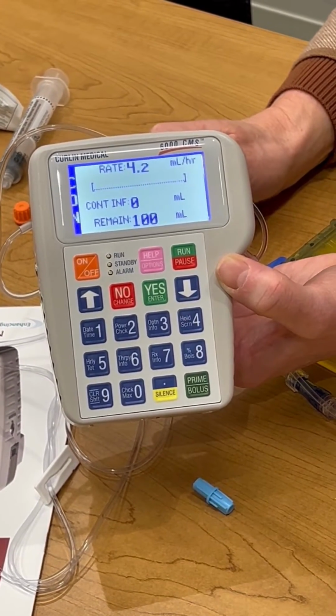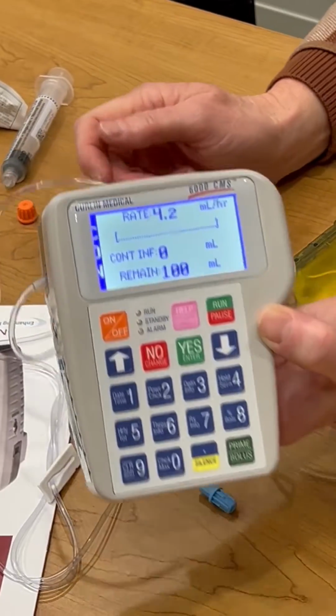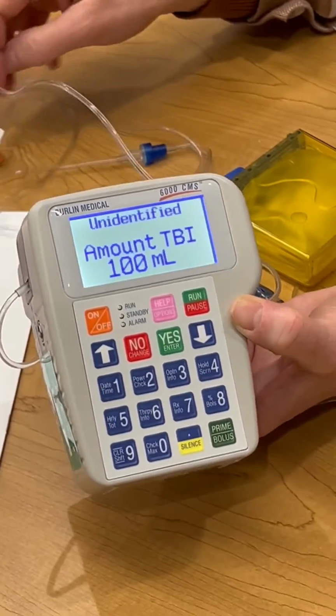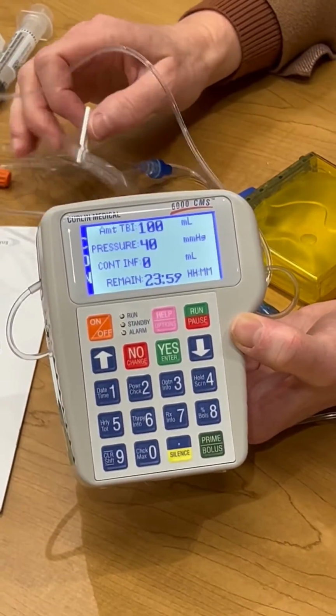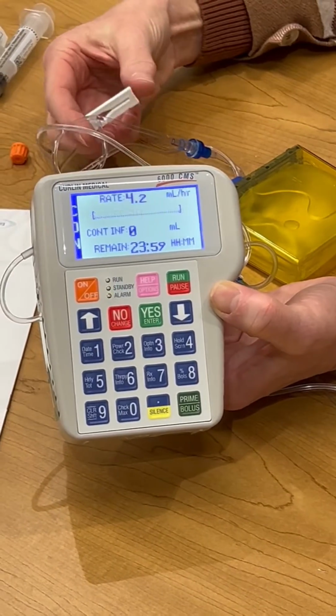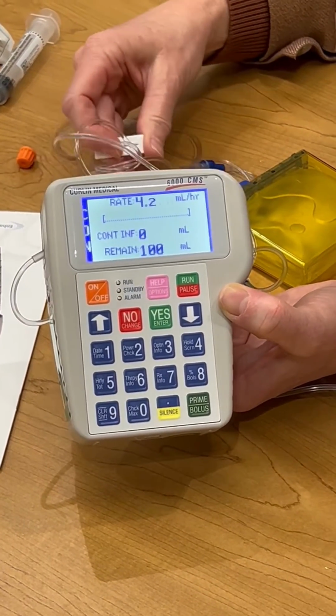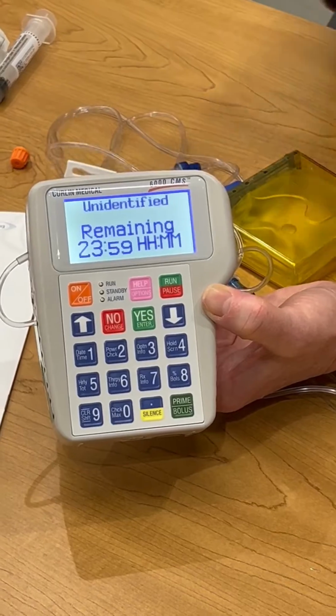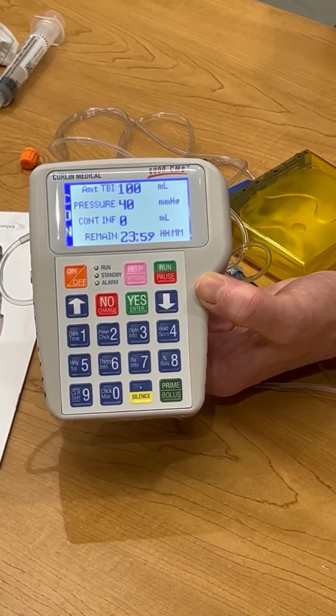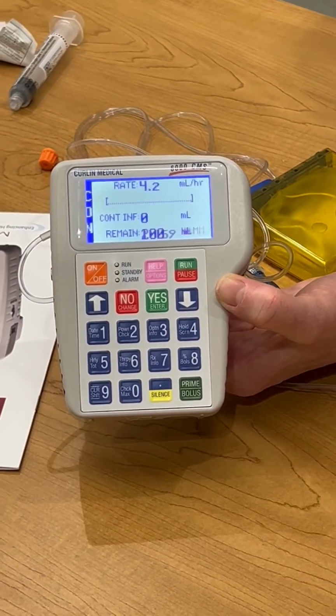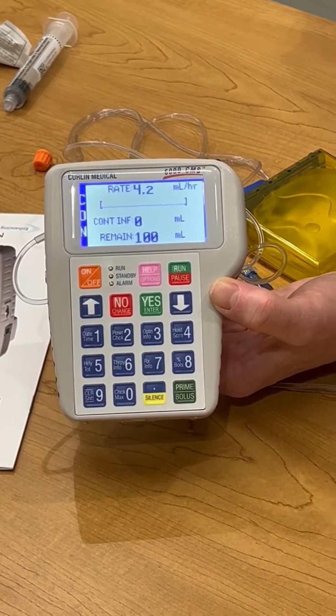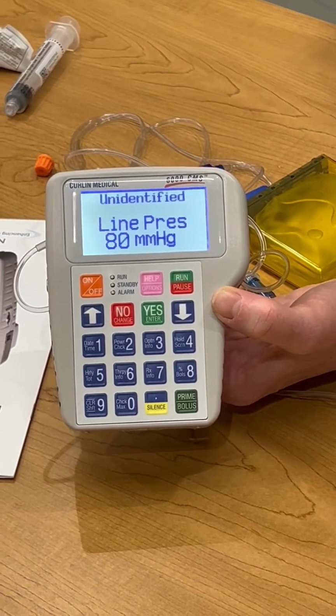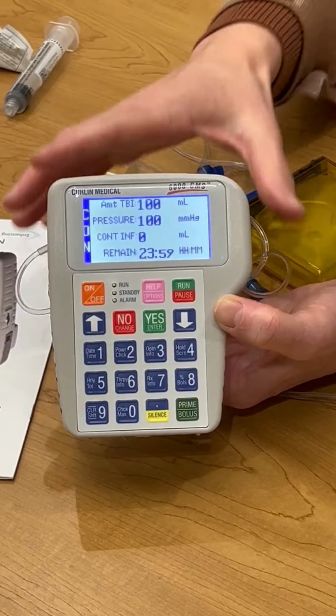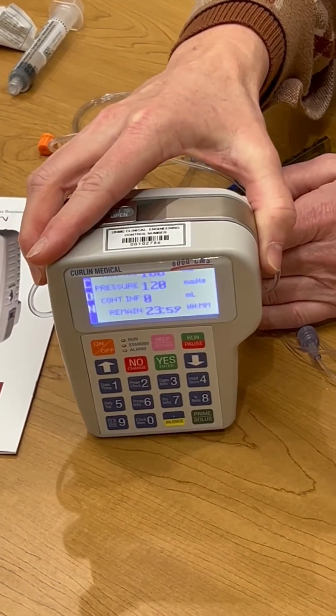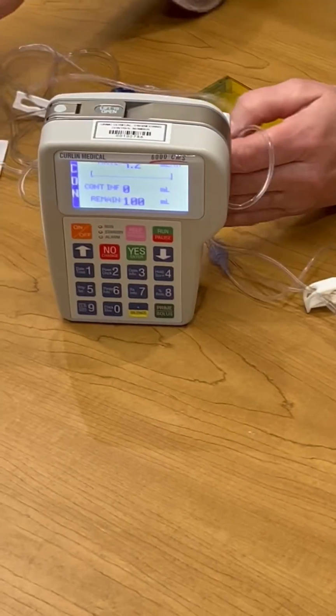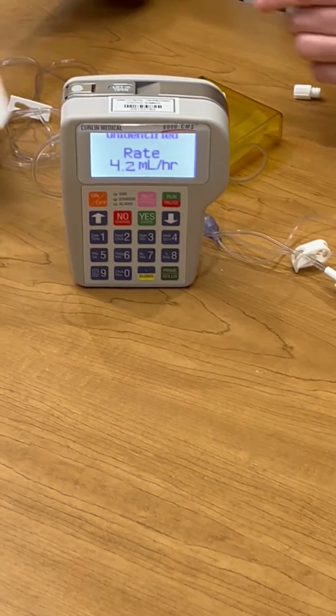If there's an issue with your pump, it's going to alarm, most likely telling you there's an occlusion. Occlusions happen when maybe you forgot to open the clamp on your tubing, or you rolled over while sleeping and kinked your line. Once you find the kink and open it up, your pump will start working again. You do have to check your alarms, because if you don't, your pump stops and you don't get your infusion.